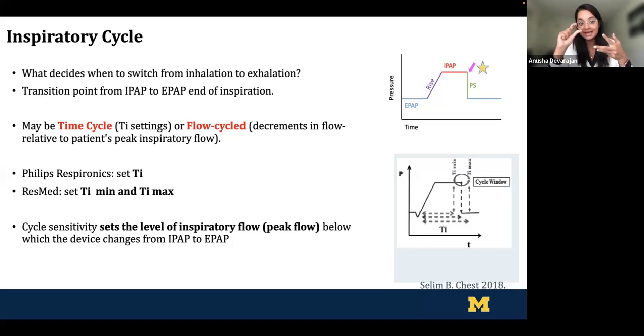And between the two, TI min is the minimum amount of time that is spent in inhalation, and TI max is the maximum amount of time that the patient gets to spend in inhalation. Obviously, you want to consider a narrower range between the TI min and max to optimize the sensitivity there and optimize the cycle so that they actually switch to expiration when the patient actually wants to exhale and they're not forced to inhale at that time.